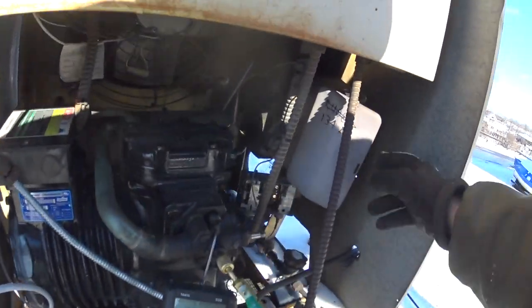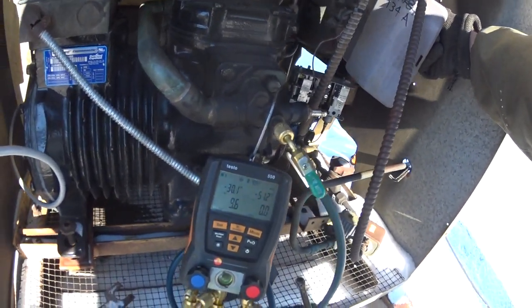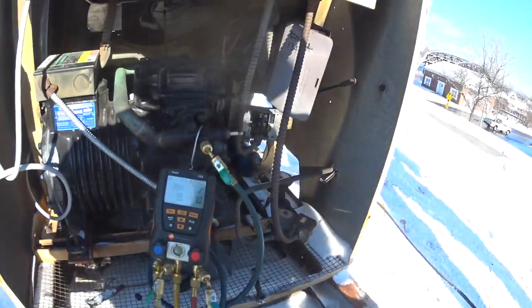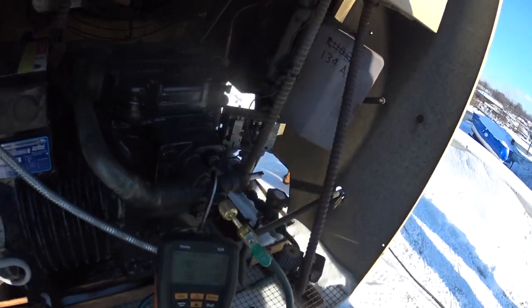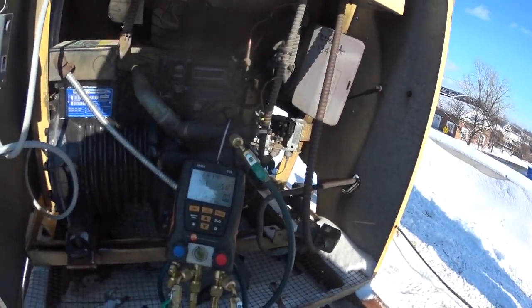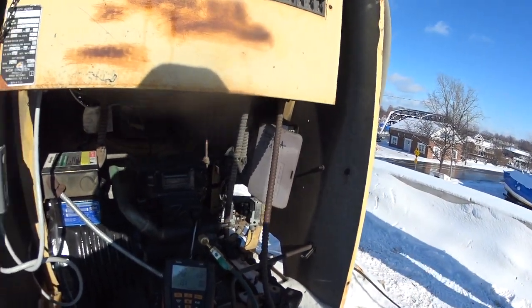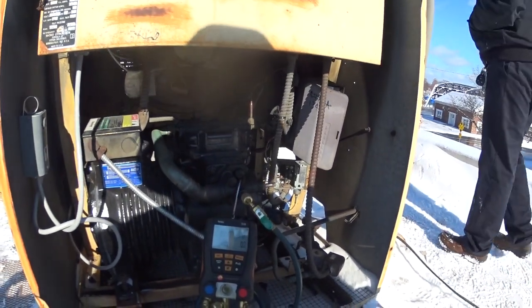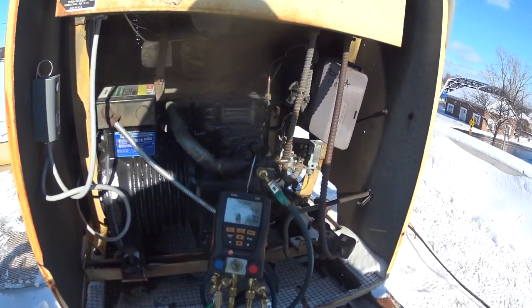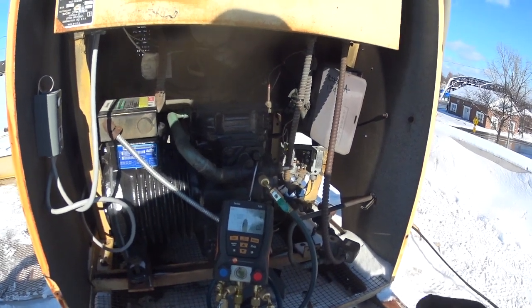Okay, it's off on the frost. I'm going to take it off now, and this should hit 20 pounds pressure because the heater's on. It gets so cold that the refrigerant just contracts. Normally when it's warm, the refrigerant's expanded enough.